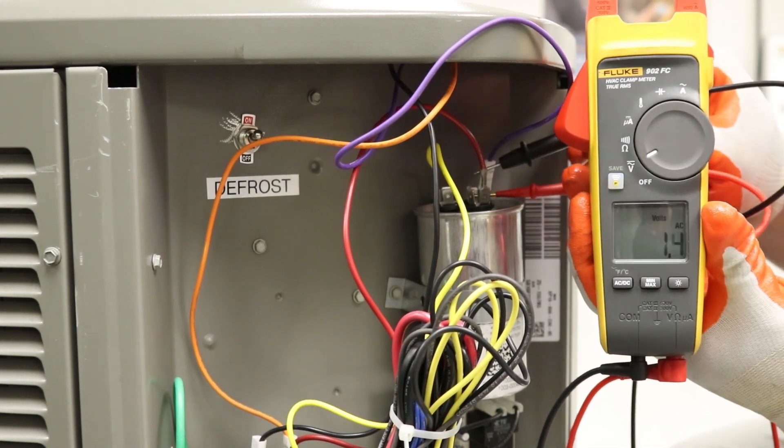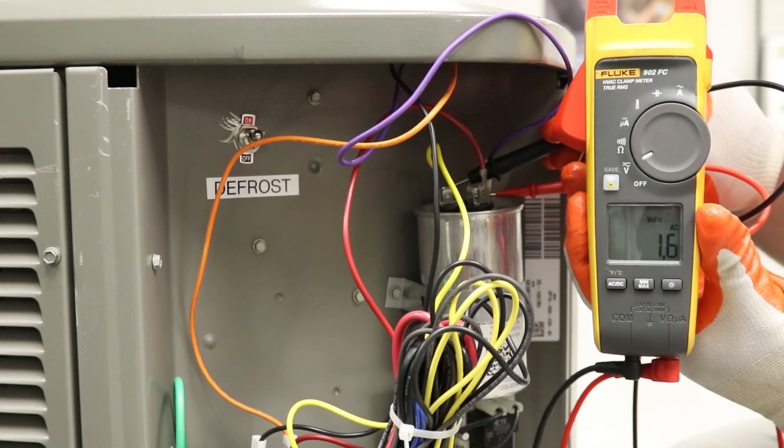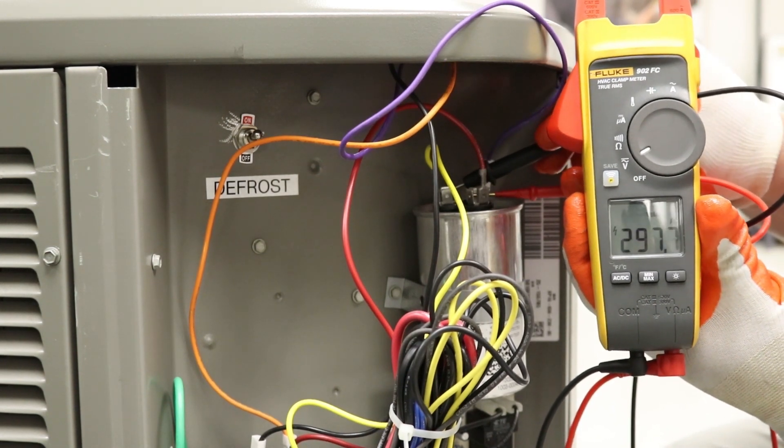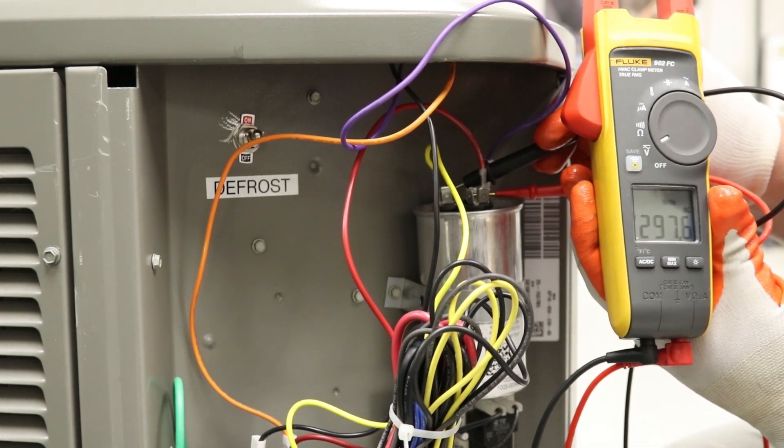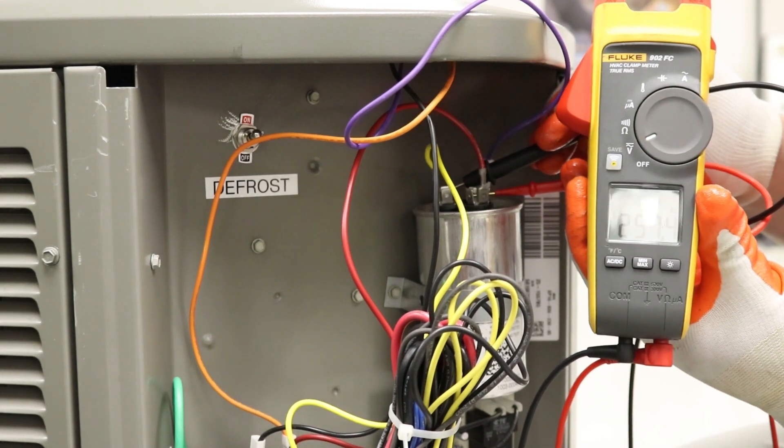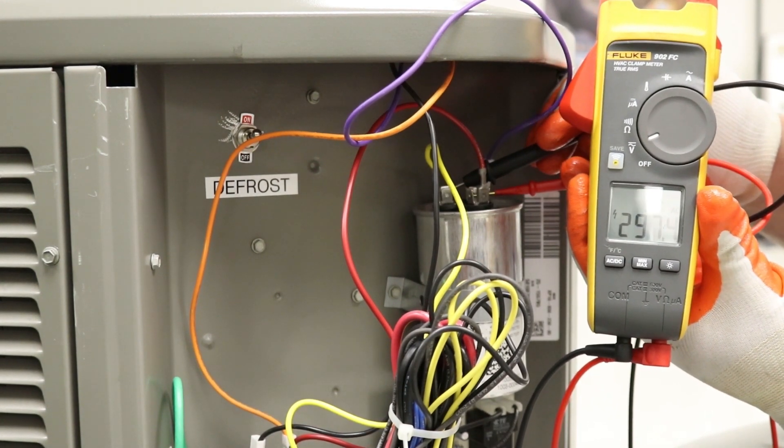And lastly, we need the number from the compressor. Same thing. We're going to go across the common terminal to the hermetic terminal. And that is going to give us 297.6 volts.